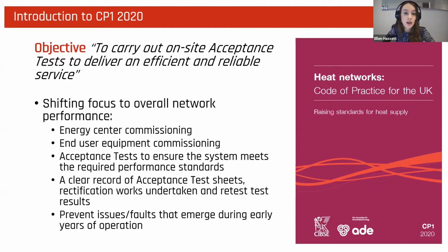So poor commissioning and performance of the energy centre is often associated with unstable flow temperatures. In the past, there's been a tendency during commissioning to solely focus on achieving stable operation during peak load, despite part load conditions being more common during operation. This hindsight leads to unstable flow temperatures during part or varying loads, risking the reliability of the heat network.